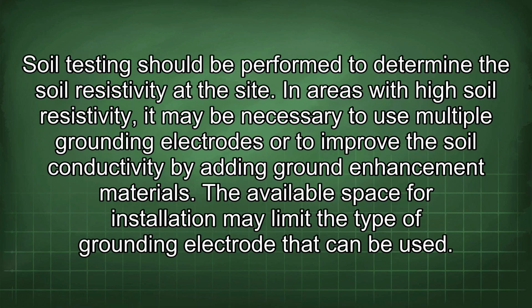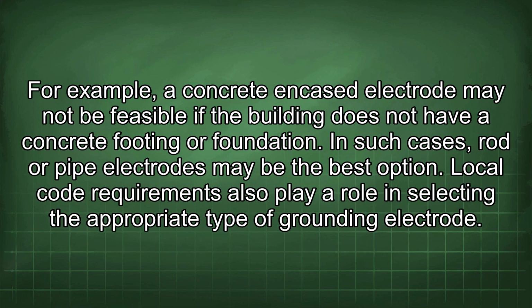Soil testing should be performed to determine the soil resistivity at the site. In areas with high soil resistivity, it may be necessary to use multiple grounding electrodes or to improve the soil conductivity by adding ground enhancement materials. The available space for installation may limit the type of grounding electrode that can be used. For example, a concrete-encased electrode may not be feasible if the building does not have a concrete footing or foundation. In such cases, rod or pipe electrodes may be the best option.